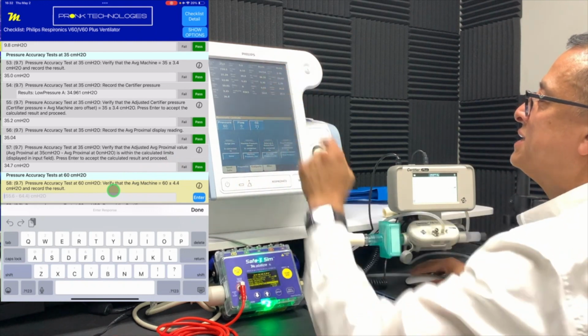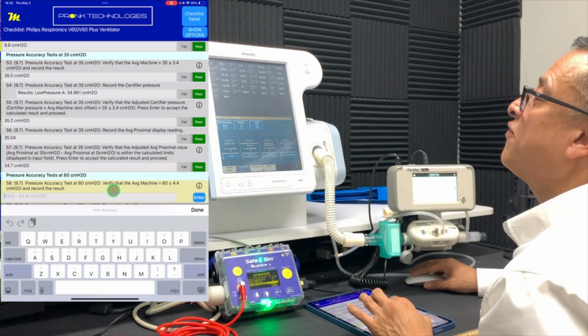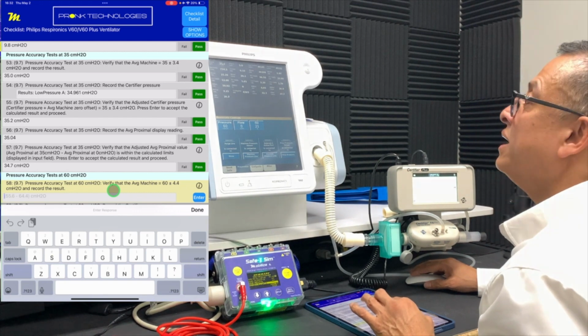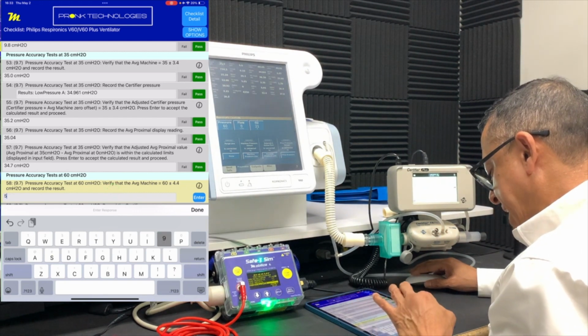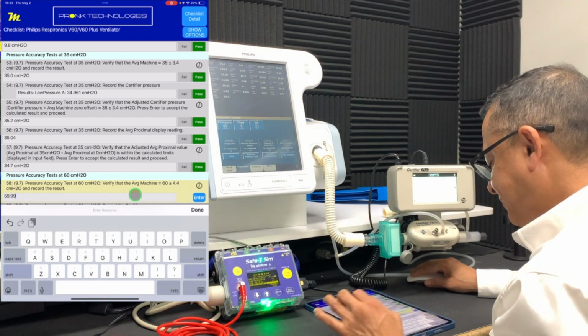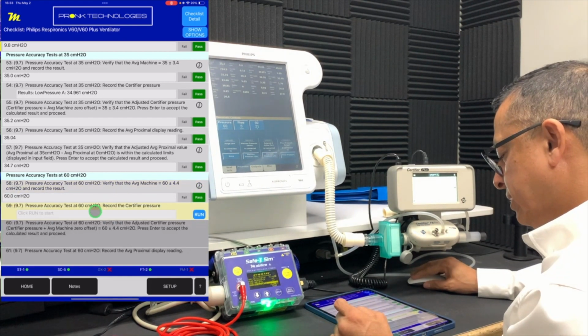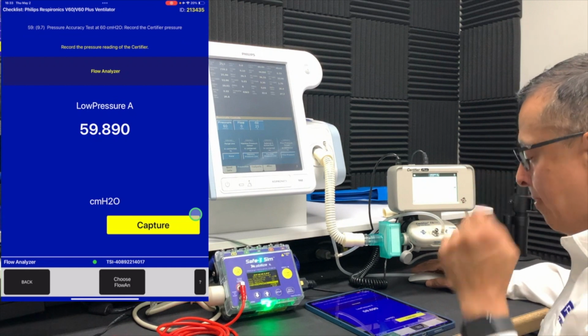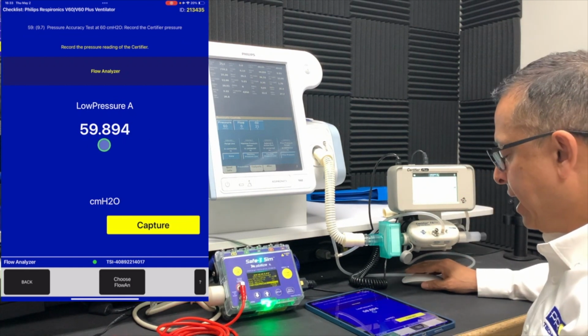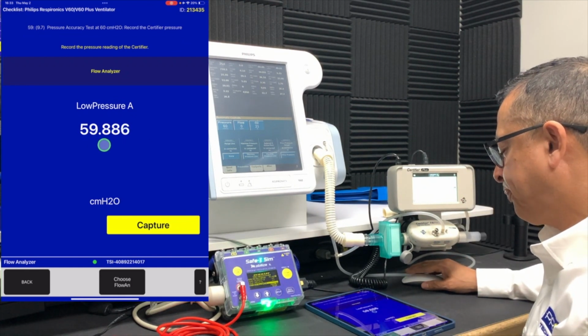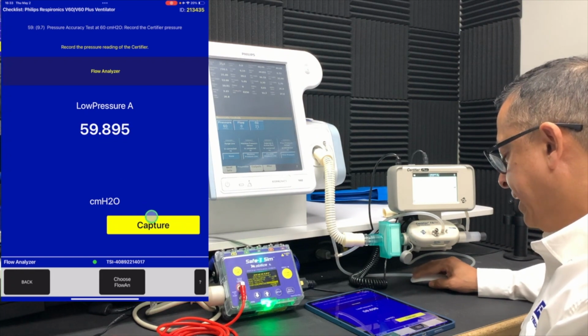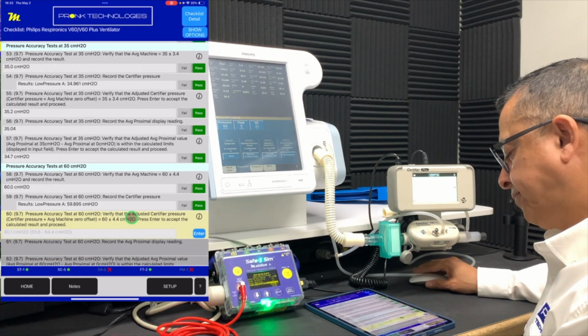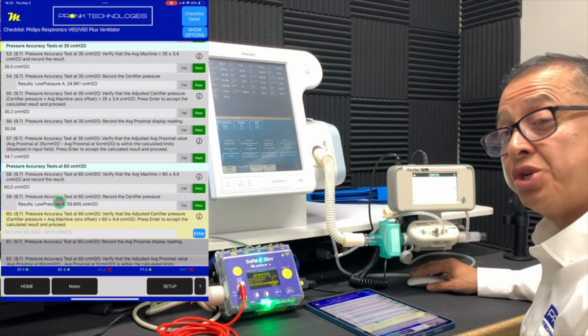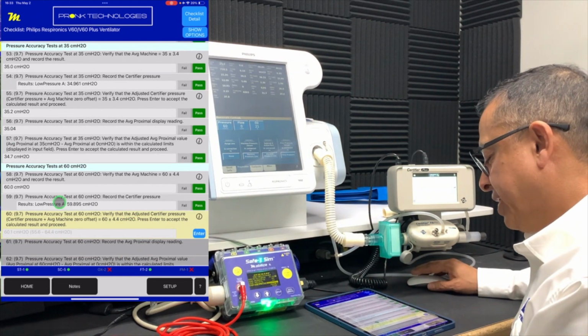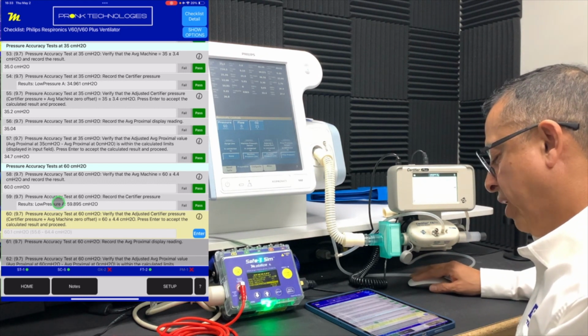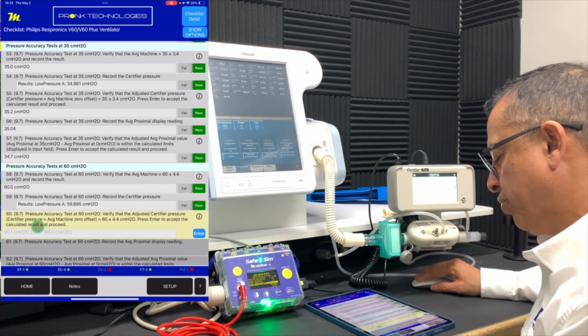Average machine pressure at 60. We'll observe it for a moment. And we'll call that 59.99. Save that. Certifier pressure at that test point, 59.89. We'll observe it for a moment, make sure it's stable, and capture that result. Again, get another calculation. The intelligent checklist calculates that for us. Well, here's the calculation within range.